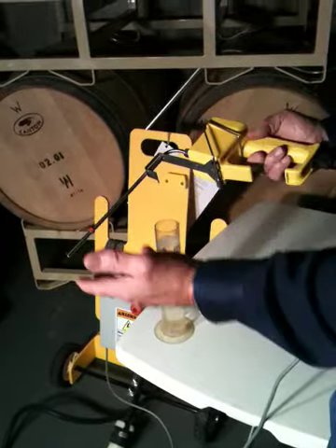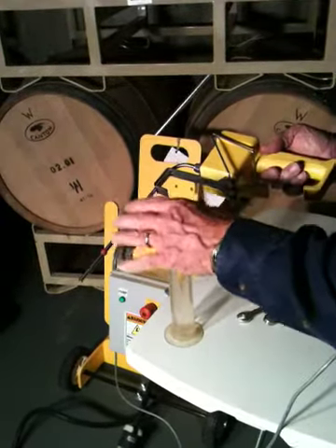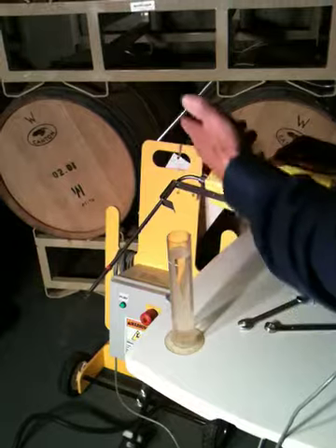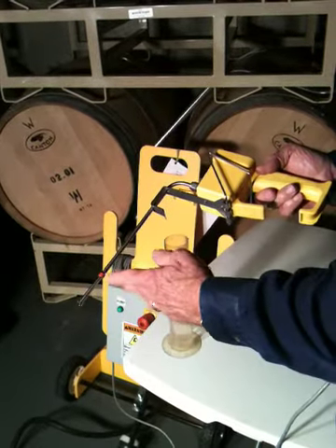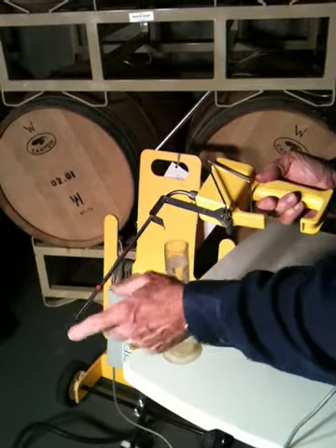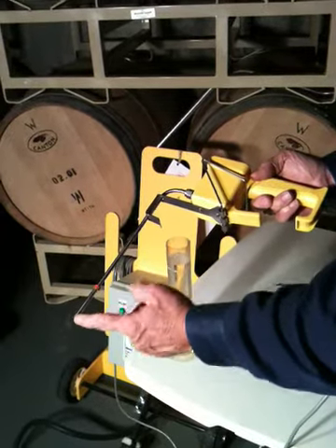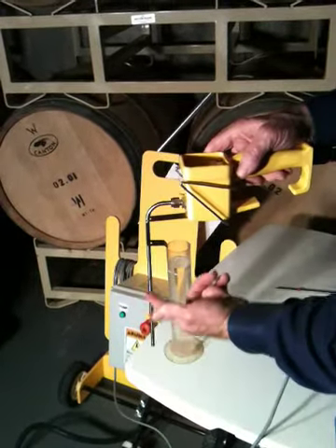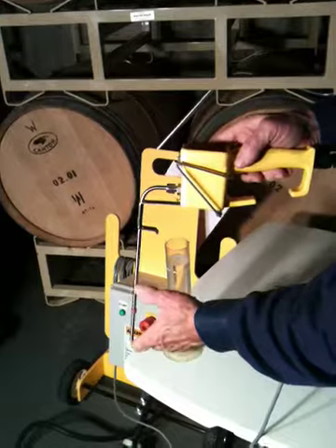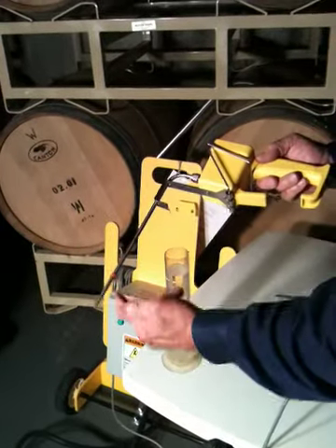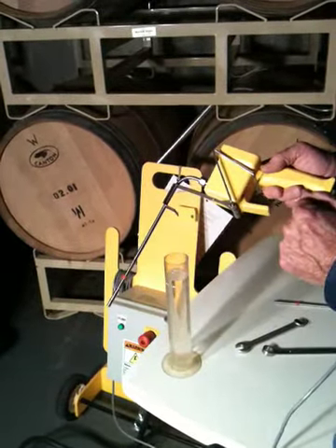Well, if you're filling a Chardonnay barrel and you want to reduce the volume fill so you have some vapor space on the top of the barrel, you can put a longer sensor tube. If you want to raise the level, you can recalibrate up to as much as 4 inches from the tip. It's always measured from the bottom of the sensing tube vertically up. So we can go 0 to 4 inches approximately. Or you can cut part of the tube off and raise the level again.